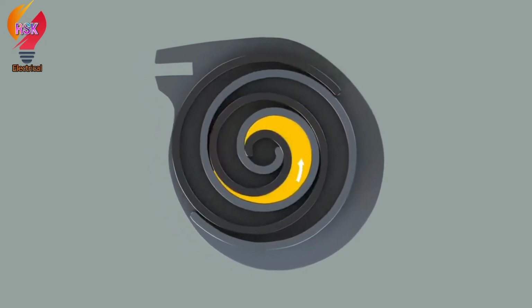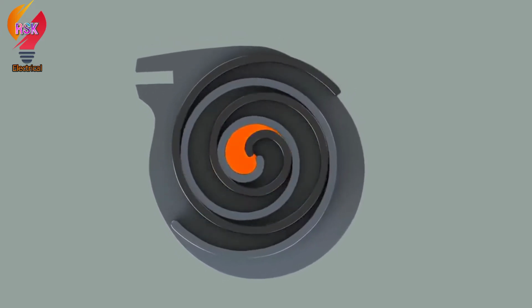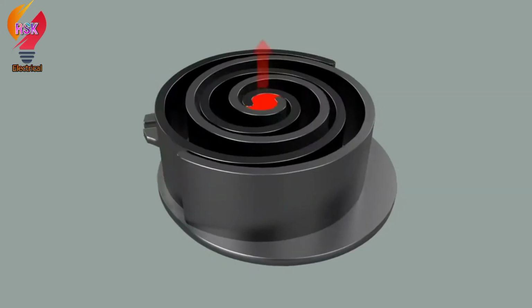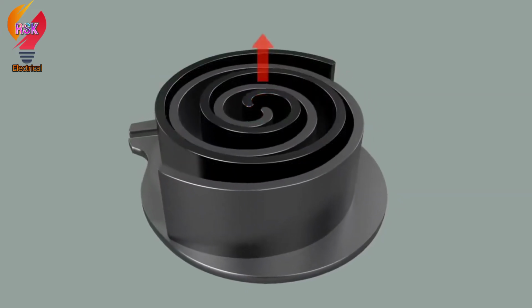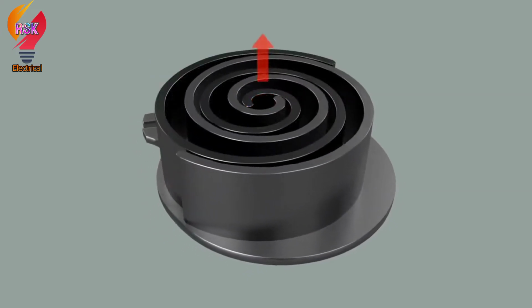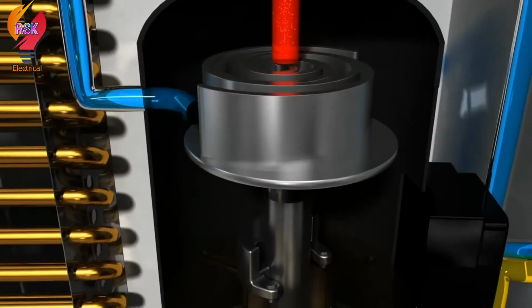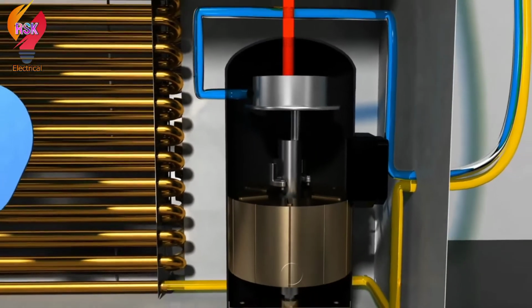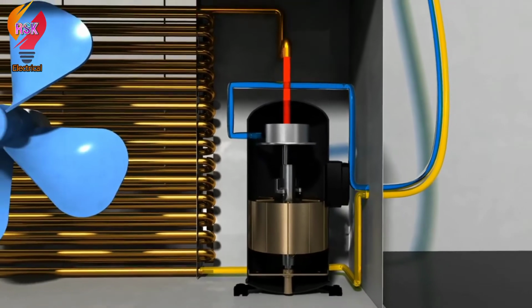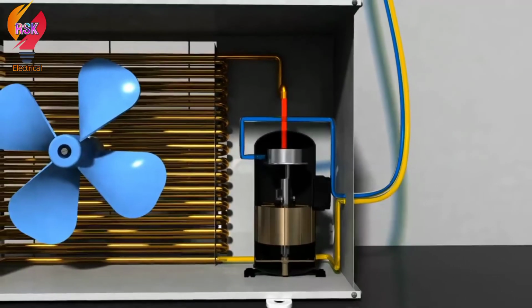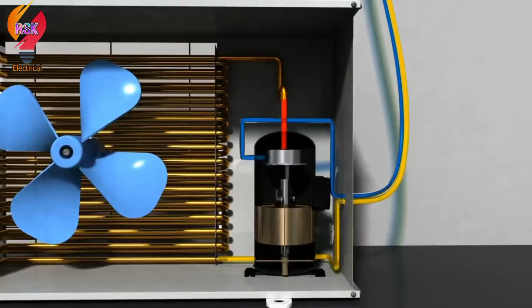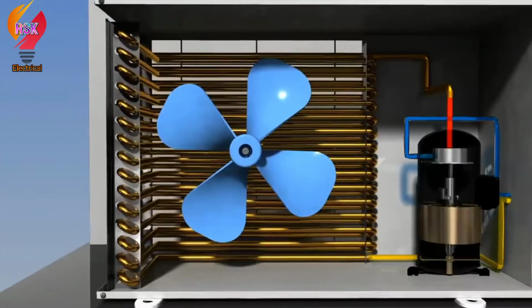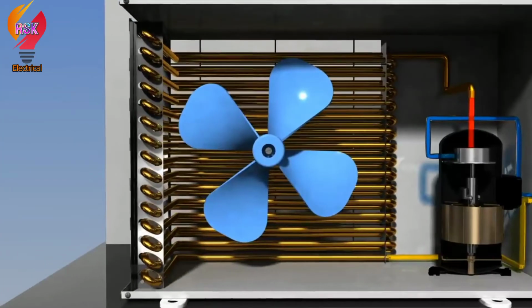As there is less space now, gas becomes more compressed and is discharged from the middle of the scroll in a compressed state. The reason for using such a type of compressor is the efficiency of space utilization. This type of compressor allows the machinery to become smaller in size and reduces noise as well as vibration. Compressed air is then sent to a condenser to be pressed into liquid.